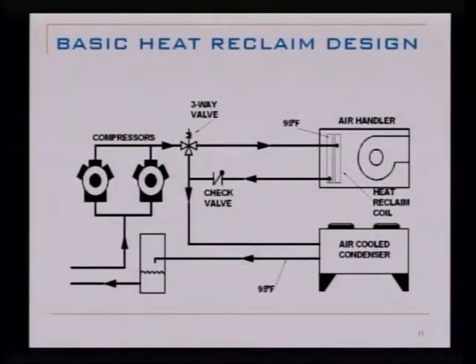This was the condenser heat reclaim off of the refrigeration equipment? Right. Instead of taking it up to the roof and putting it through the condenser, or before you take it up to the roof and put it through the condenser, putting it into the main air handler unit. And I'll show you some pictures about that in just a minute here. So that's the basic picture of how I'm proposing that heat reclaim be done. There are a lot of different ways that heat recovery has been done and is done in refrigeration systems, but this is the methodology that I'm proposing here tonight, and it's basically just that.